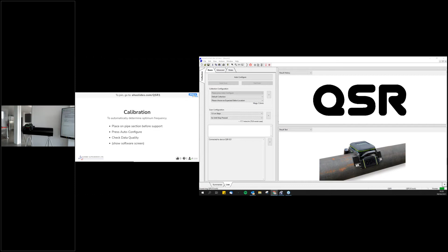Right. So the next step is calibration. When it comes to the QSR1, the term calibration will vary from equipment to equipment. But for the purpose of QSR1, calibration involves a configuration step that the QSR1 will automatically perform in order to determine the optimum inspection settings. This is all done automatically. All we've got to do is just press the auto configure button over here.